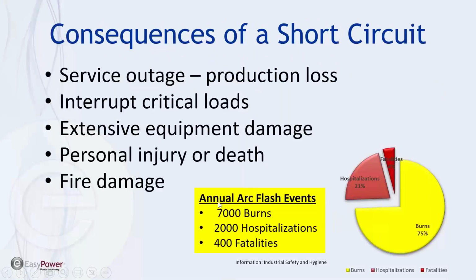So as far as the consequences from a fault, these are just some of the things that can happen. Service outage, production loss. That can amount to quite a bit of losses, depending on what the outage is. You may interrupt critical loads if you're not coordinated, that we talked about. So you're taking out power to a lot of places that shouldn't have been without power. And hopefully critical loads like that are on a transfer switch with a generator. So if the power does go out, it provides power for those critical loads, ventilation or other kinds of equipment that would require emergency use of equipment and so forth.